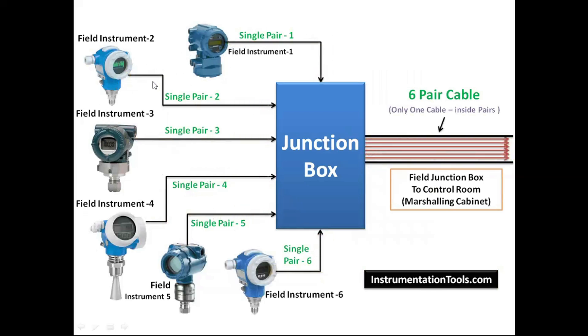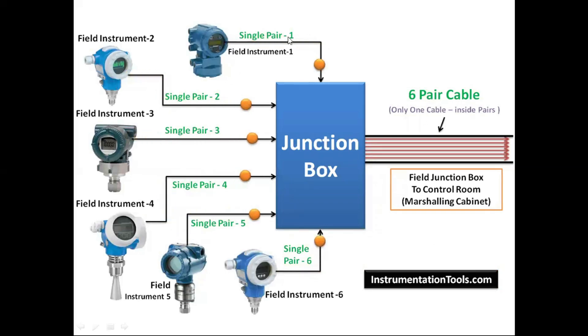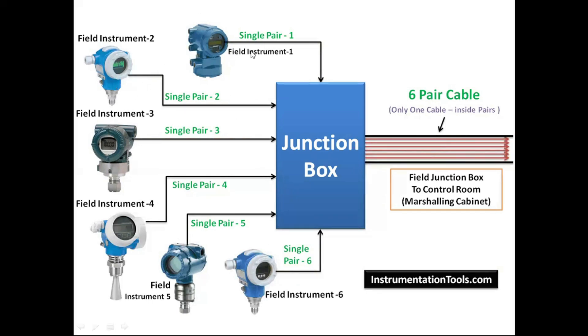For example, six sensors in the field produce 4 to 20 milliampere signals that go to the junction box present inside the field. From the junction box, the signal goes to the control room via a six-pair cable — since there are six instruments, each instrument requires two cables, making six pairs in total. The signals from all instruments are accumulated in the junction box and then routed to the control room.